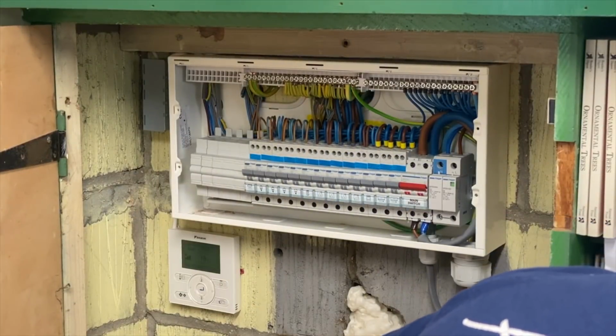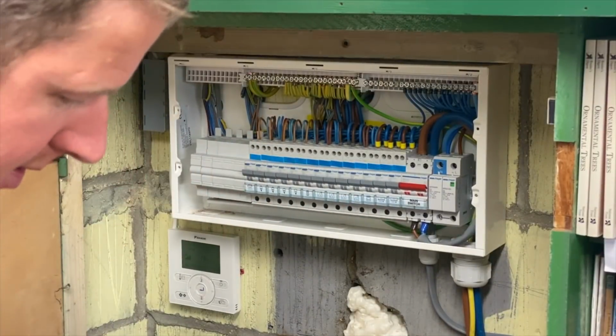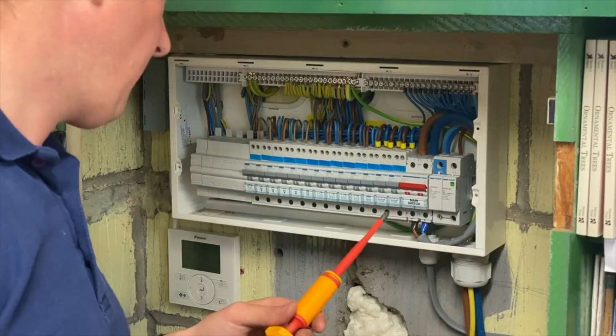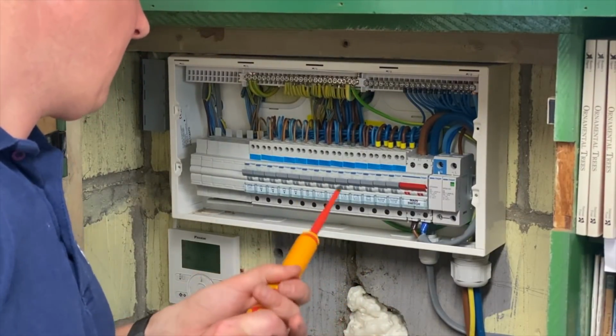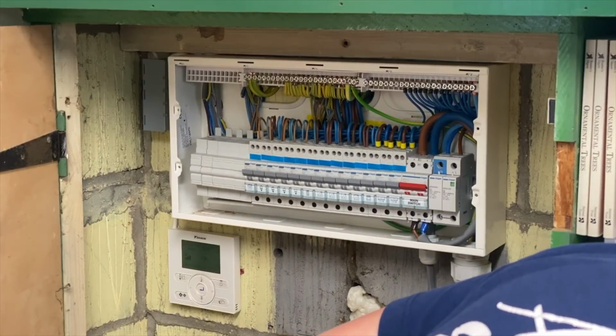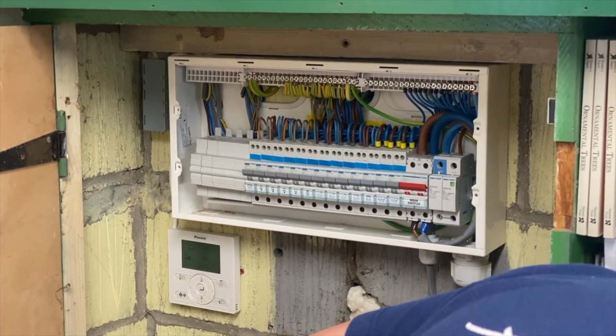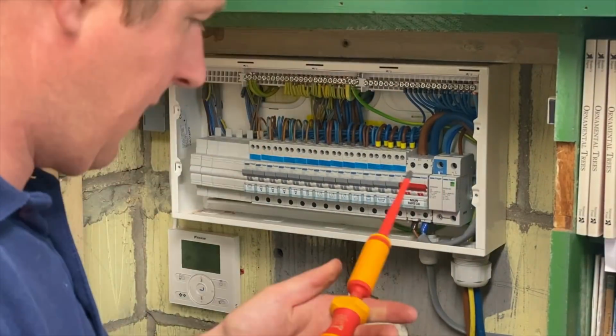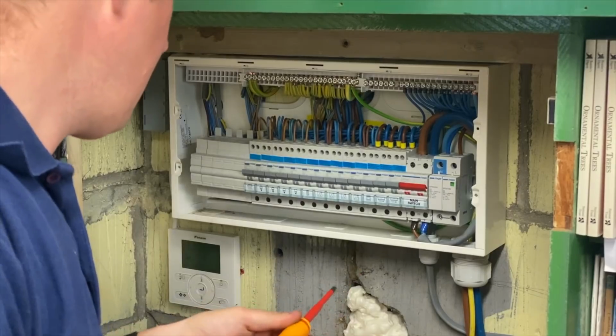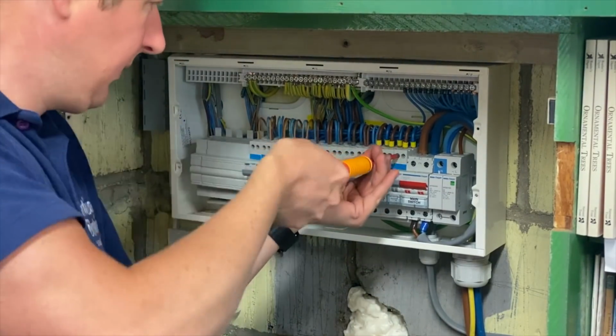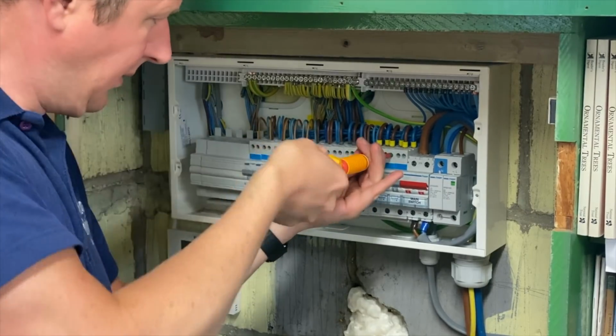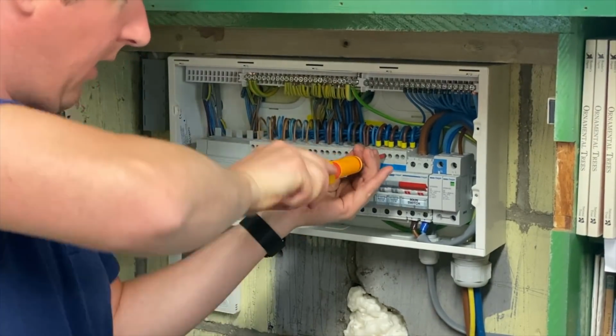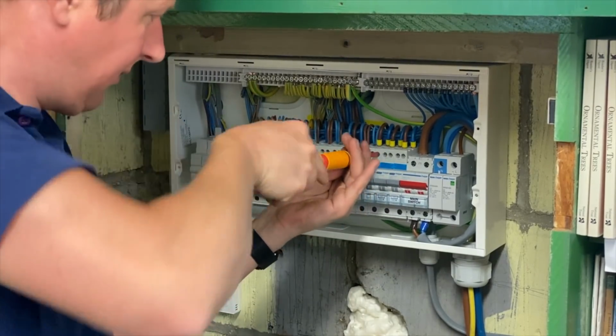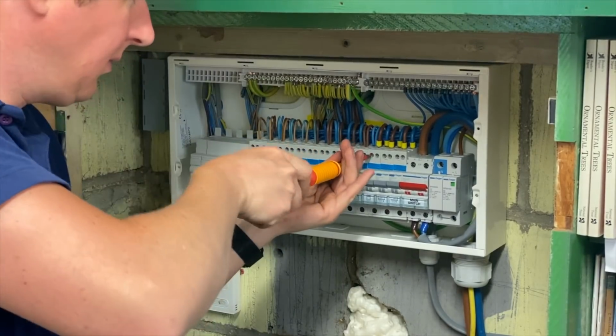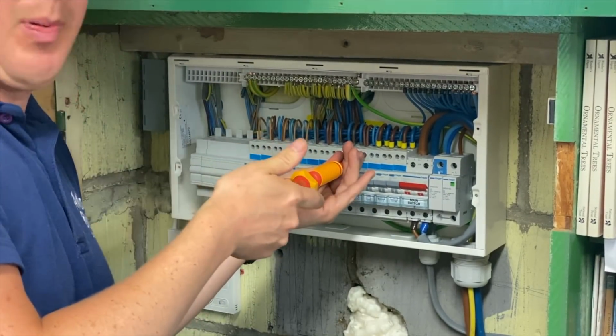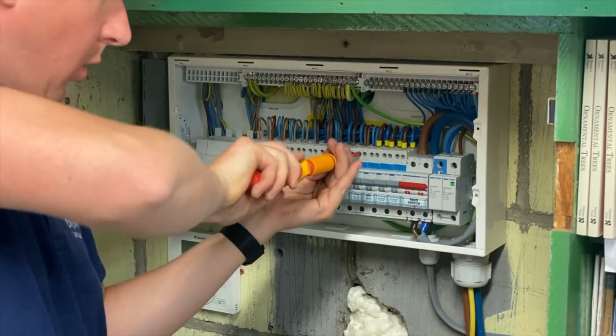Then, isolation switch disconnectors 3.6 Newton meters. So unfortunately this torque screwdriver only goes up to 3 Newton meters. So I'll do that at the end. MCBs and RCBOs, we need 2.1 Newton meters on all of the connections. So we'll go up by 1 Newton meter and we'll just do all of these. You can see how much more torque we're getting on these. And that click, by the way, is just so that it tells you when it's reached the correct torque.